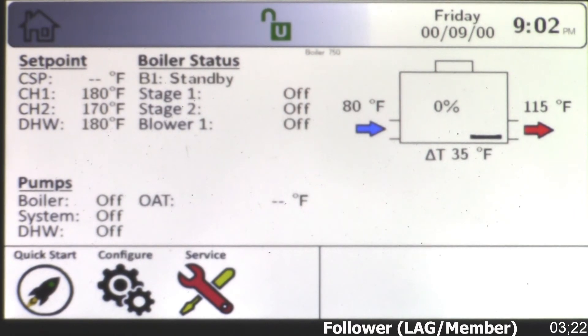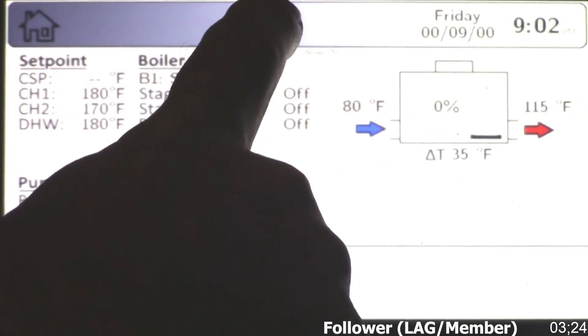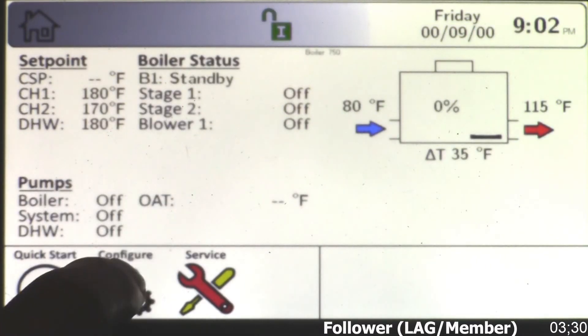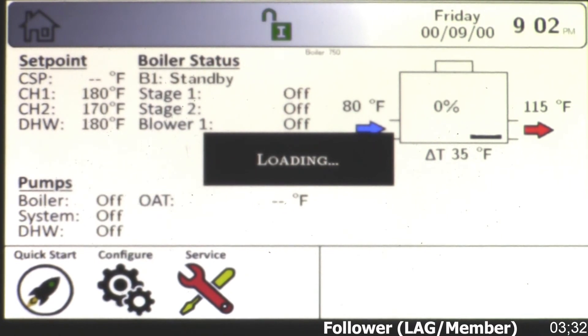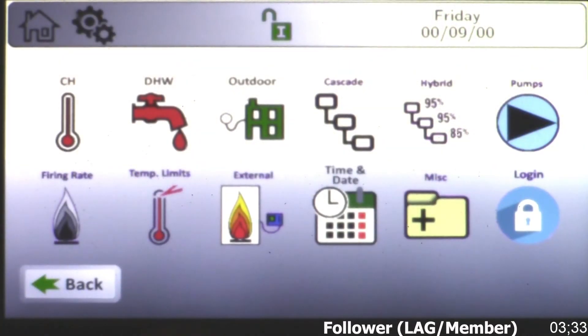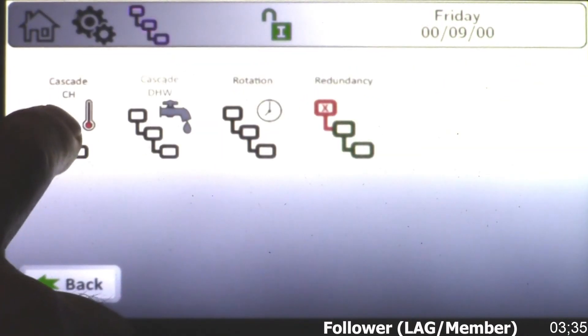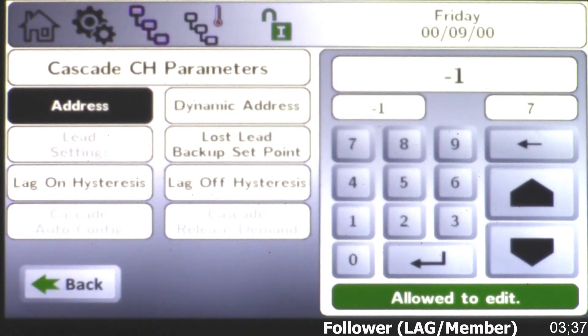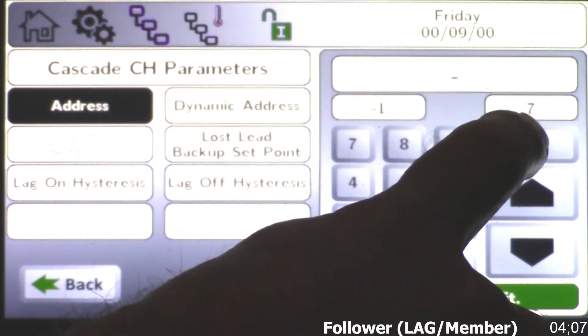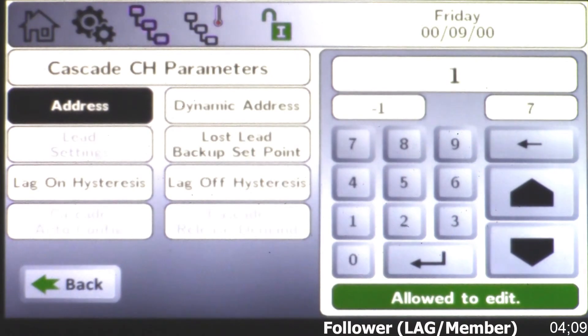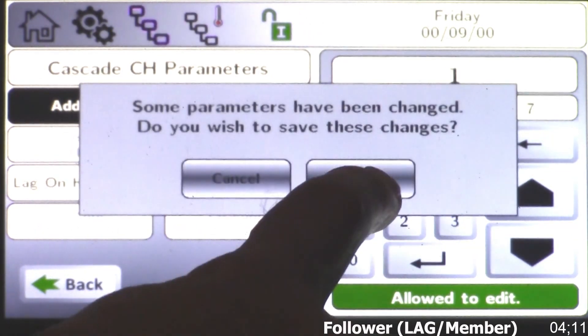Over here on my first lag boiler, again you'll have to log in — typing in 17, enter. Going to go to configuration, cascade. In our example we're doing central heat. Here I need to give this an address, and my first member or lag boiler becomes one. I'll back this out and choose the value of one, then enter.